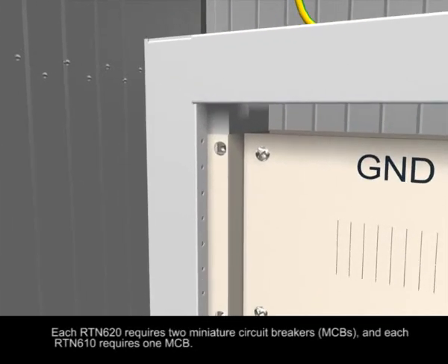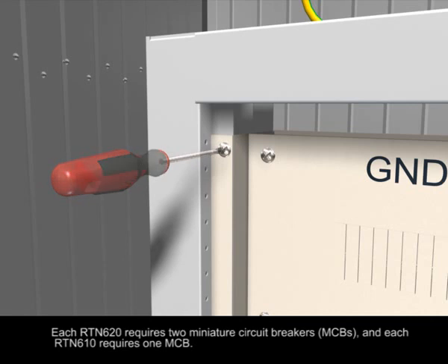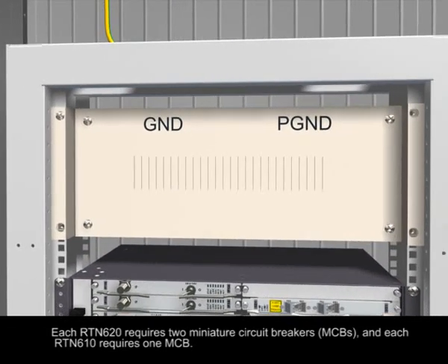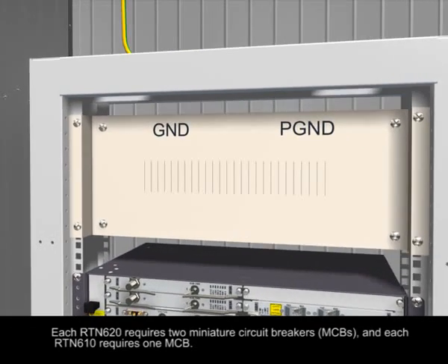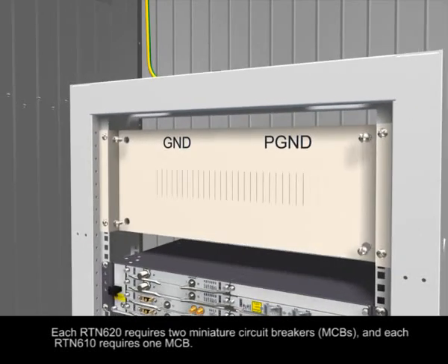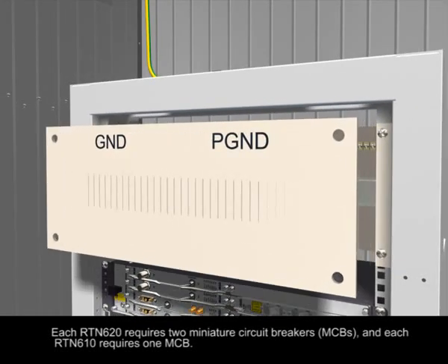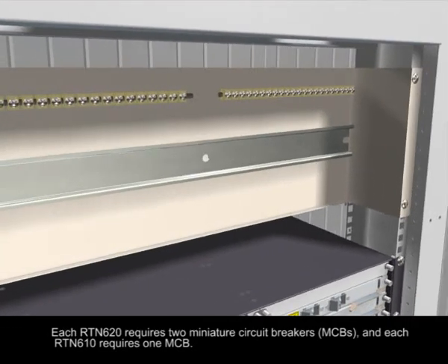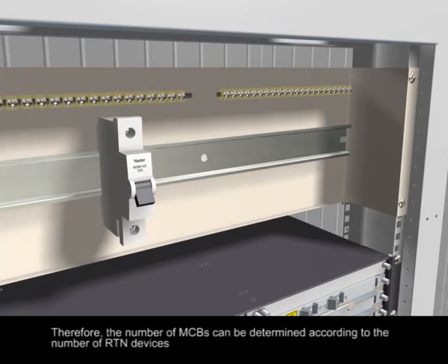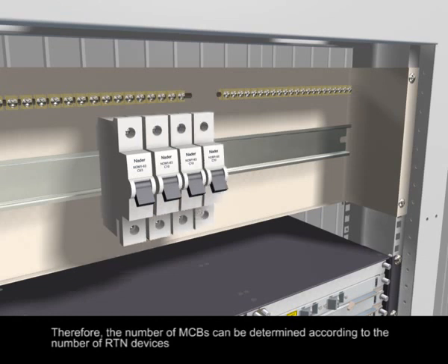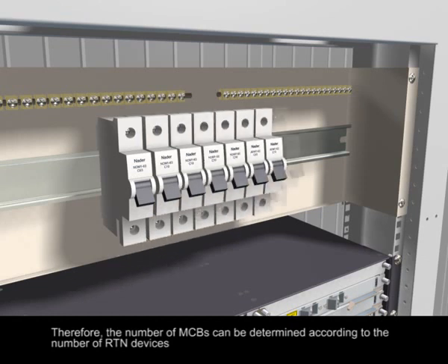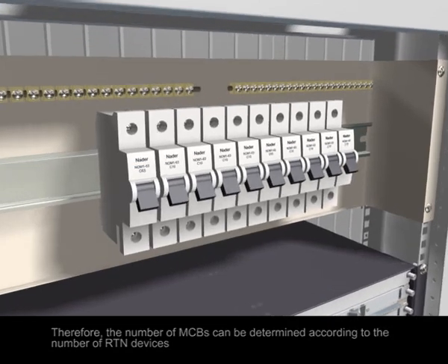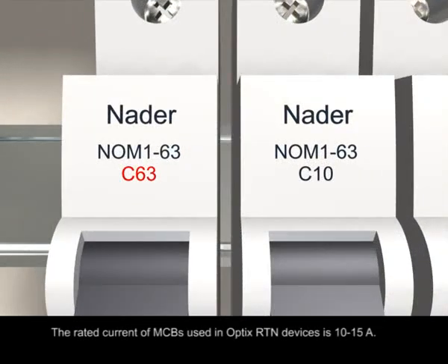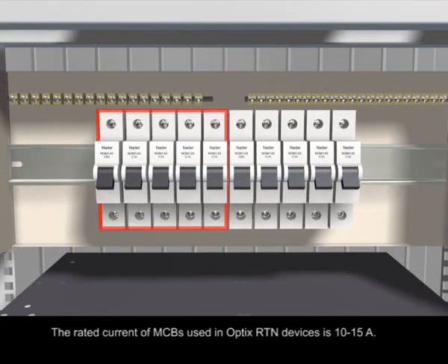Each Optix RTN 620 requires 2 miniature circuit breakers, hereafter referred to as MCBs, and each Optix RTN 610 requires 1 MCB. Therefore, the number of MCBs can be determined according to the number of Optix RTN devices. The rated current of MCBs used in the Optix RTN devices is 10 to 15 amperes.